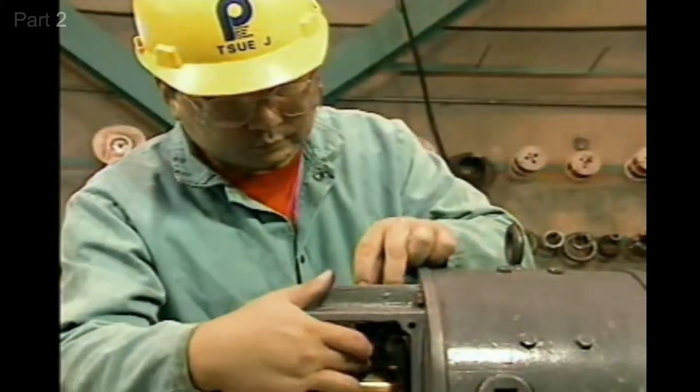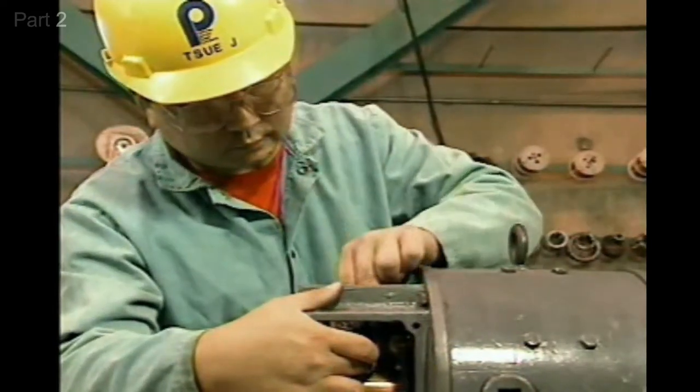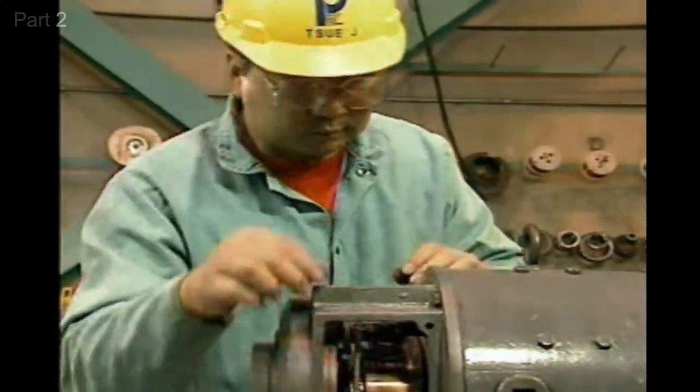The inside surfaces of the brush holders should be checked to make sure that they're clean and smooth. Any burrs or dings must be removed with a file or sandpaper. If they're not removed, a brush could get hung up on them and not make good contact with the commutator.